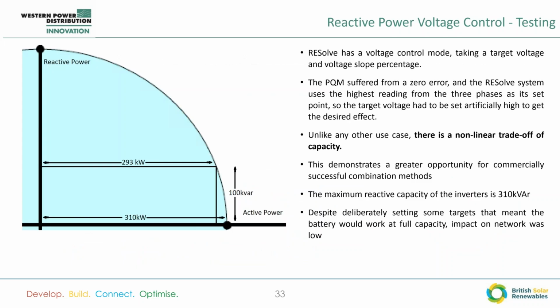Now, the interesting thing is that unlike every other use case, if you want to offer 100 kilowatts of network support, you have to take 100 kilowatts away from your base case. But with reactive power, due to operating on this curve, the inverters can actually do two things at once. So by giving up 17 kilowatts of active power, you can offer 100 kVAR of reactive power support.